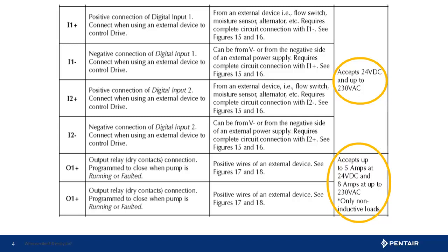The output can as well take the same range of voltage, but is limited on how many amps, as you see here. More importantly, no inrush current, meaning no motors, say a dosing pump, can be connected. So, what can be connected? A simple alarm, a light, or a magnetic relay or pump start relay.